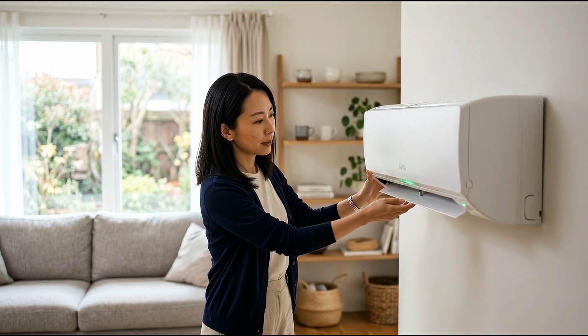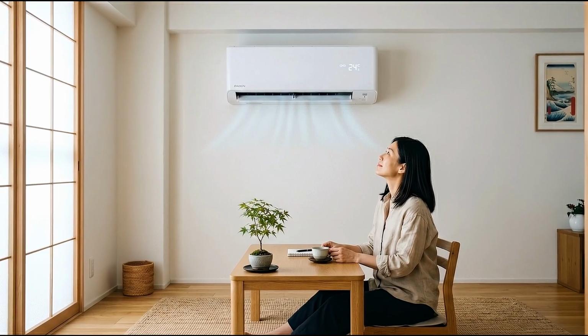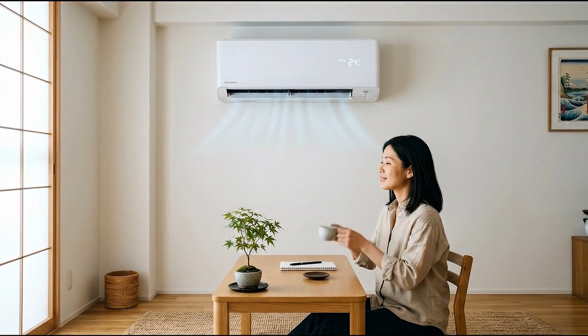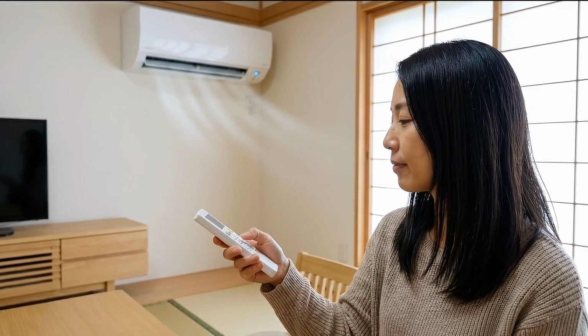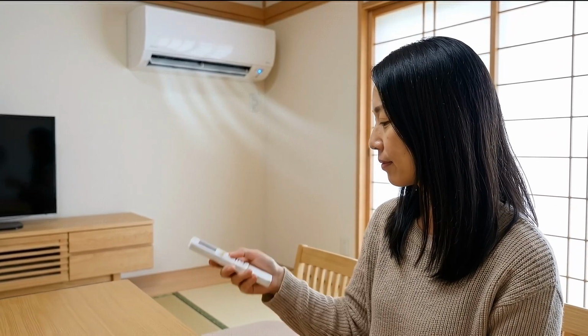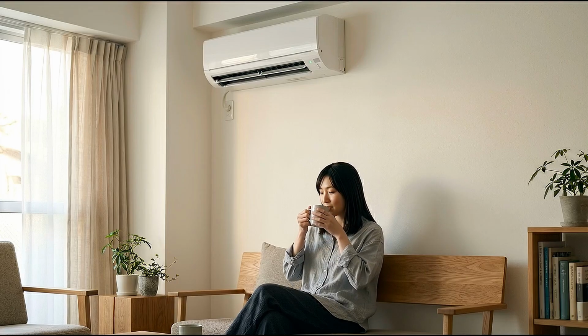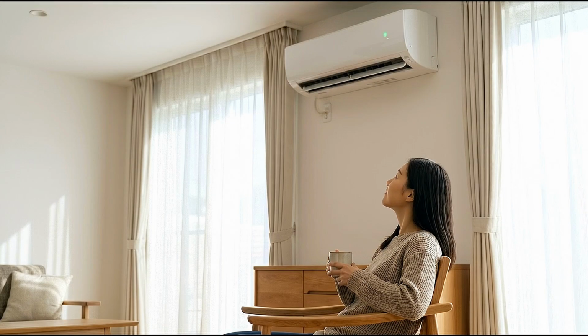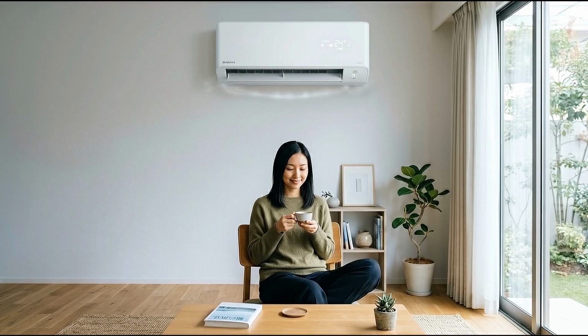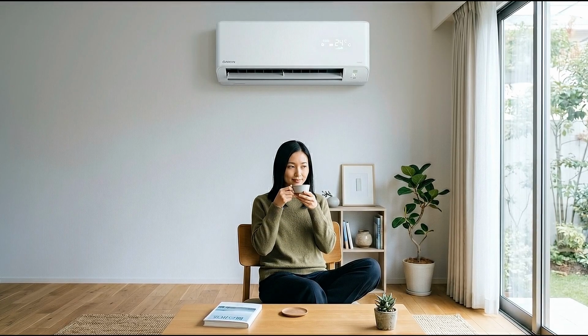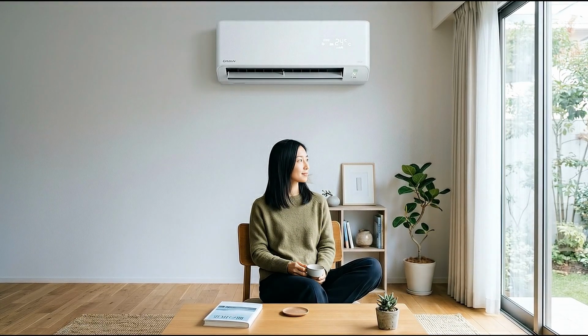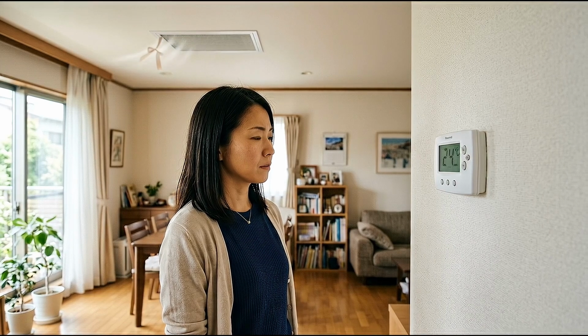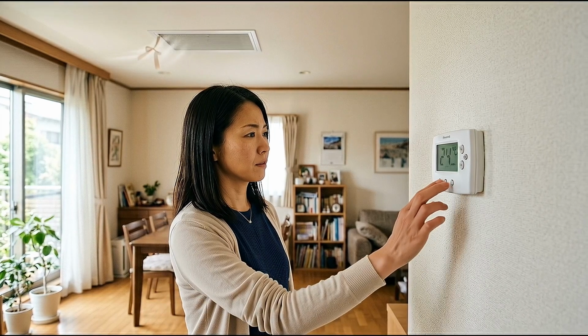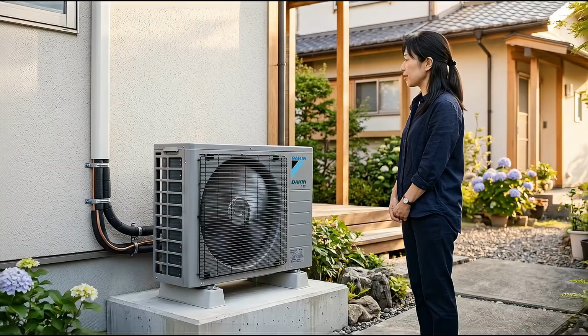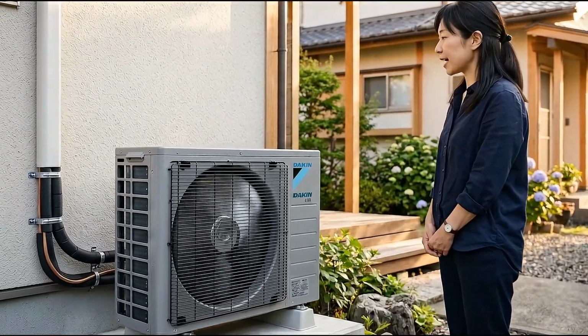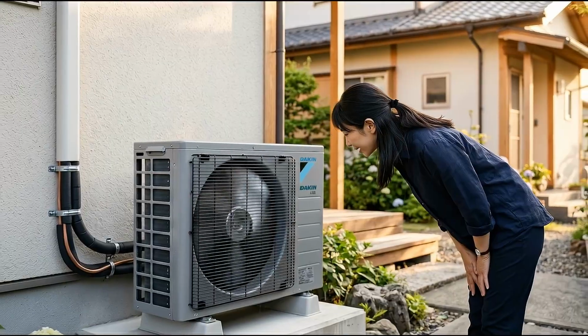There is also a technology difference worth mentioning. Inverter-based mini-splits, which dominate the Japanese market, use a variable speed compressor that adjusts its output to match the cooling load. When the room is almost at the target temperature, the compressor slows down instead of cycling off and back on. That constant adjustment uses less energy than the on-off cycling of a standard central air compressor, which runs at full speed until the thermostat is satisfied and then shuts off entirely. The inverter approach is more efficient, and it is also gentler on the compressor because it avoids the surge of a cold start every time it kicks in.